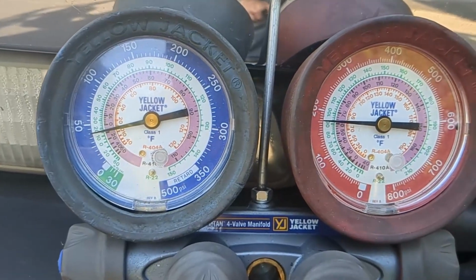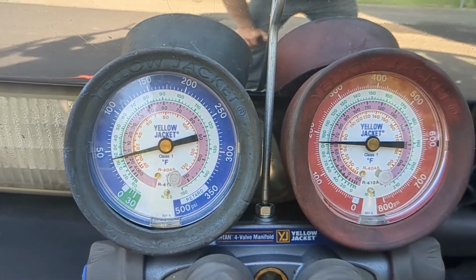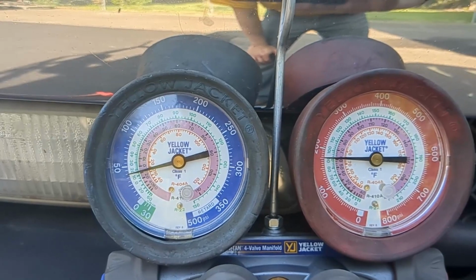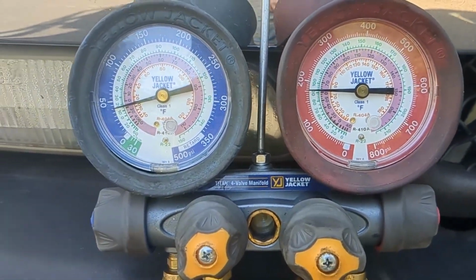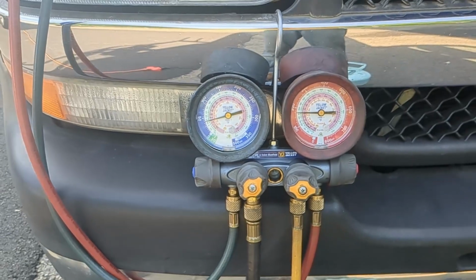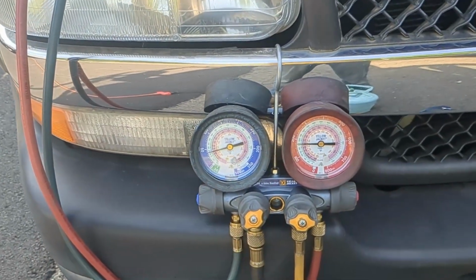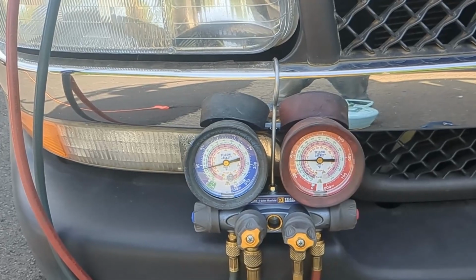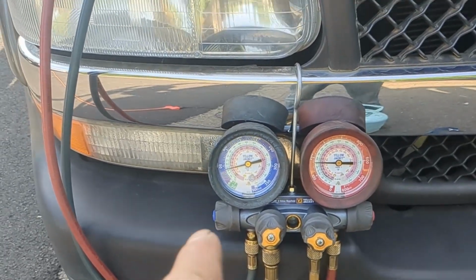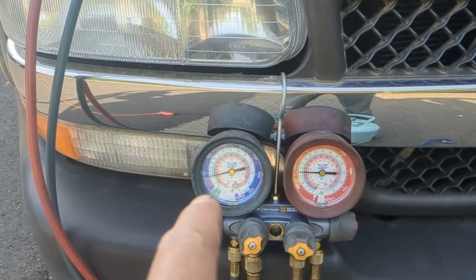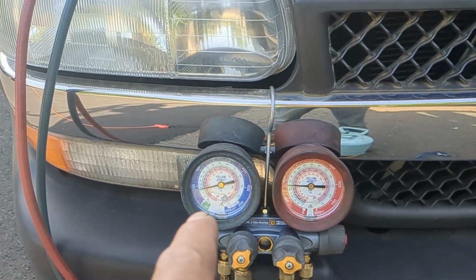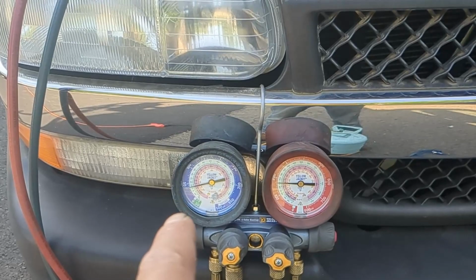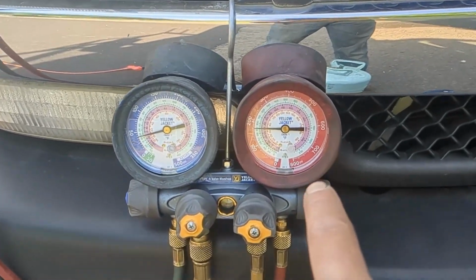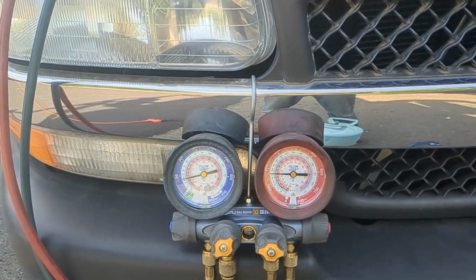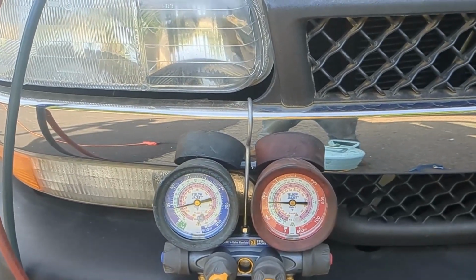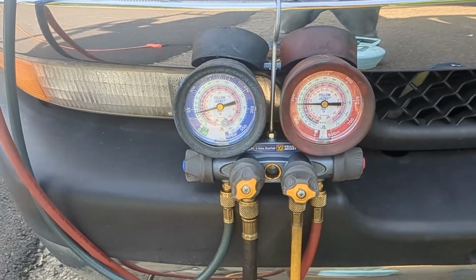So this is what I'm running: low side 40 psi, high side about 175 psi. On the low side, I'll look at the chart — I have a note on my phone — that should correspond to about 45 degrees on the R134A chart. When you look up 40 psi low side and 175 high side, that should be about 117 degrees Fahrenheit, I think.